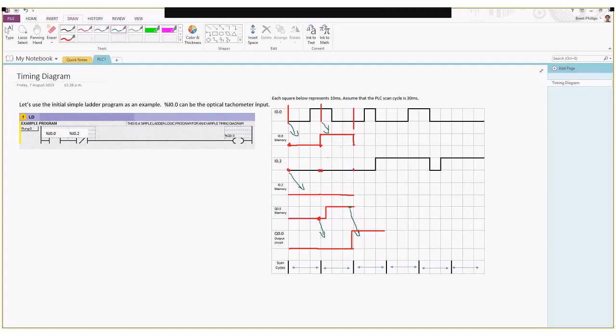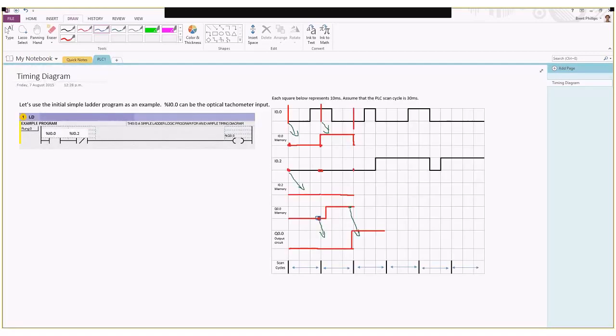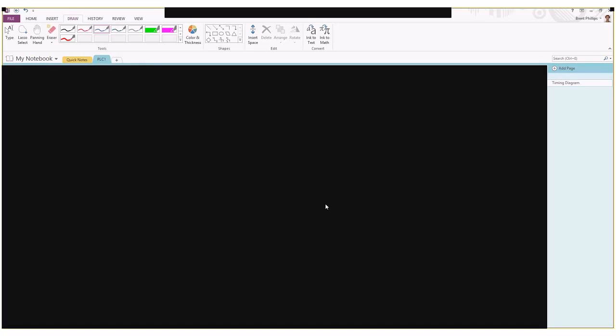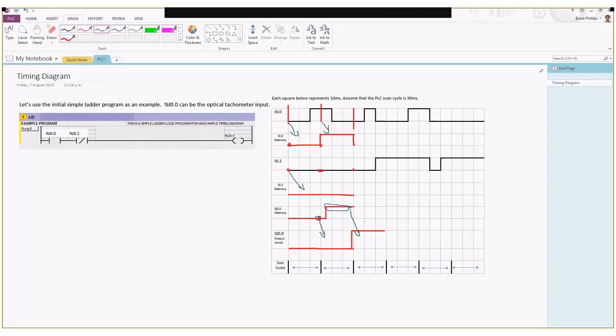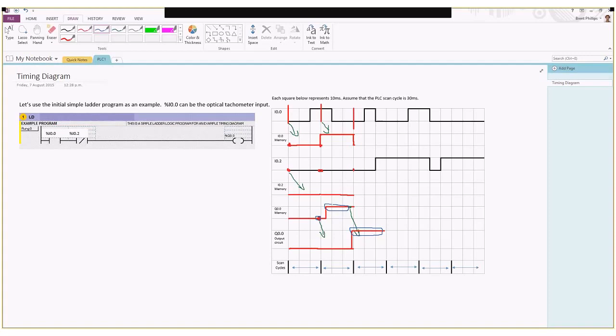Hopefully that's a good starter to show you what's going on with this relationship where we have some short delays. We have the inputs being read into memory at the start of our scan cycle, and in the middle of the scan cycle we have the input memory values being used to generate the output memory value. Then at the end of the scan cycle, that output memory value gets transferred to be a physical output value. There's always going to be a delay between the value that the logic puts into memory, and then a short time later at the end of that scan cycle, that value gets transferred to the physical output circuit.